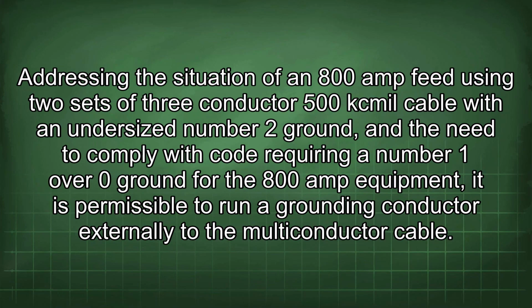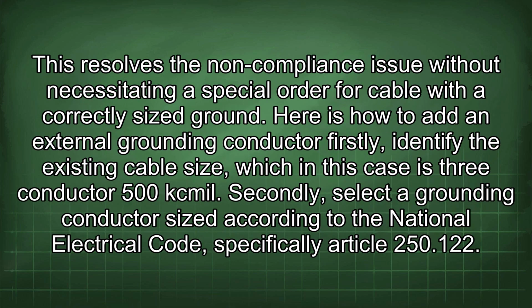Addressing the situation of an 800 amp feed using two sets of 3-conductor 500 kcmil cable with an undersized number 2 ground, and the need to comply with code requiring a number 1/0 ground for the 800 amp equipment, it is permissible to run a grounding conductor externally to the multiconductor cable. This resolves the non-compliance issue without necessitating a special order for cable with a correctly sized ground. Here is how to add an external grounding conductor.